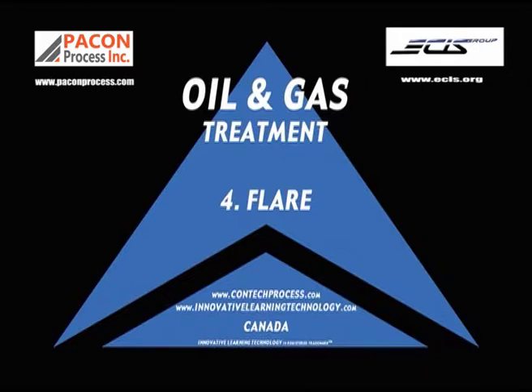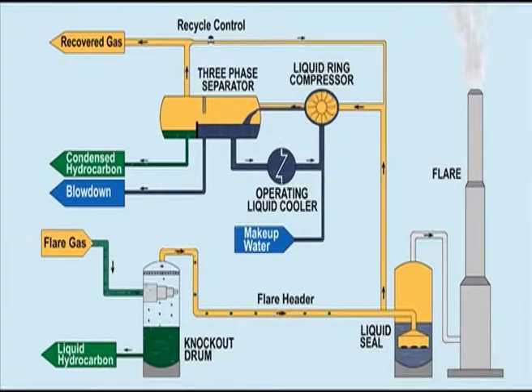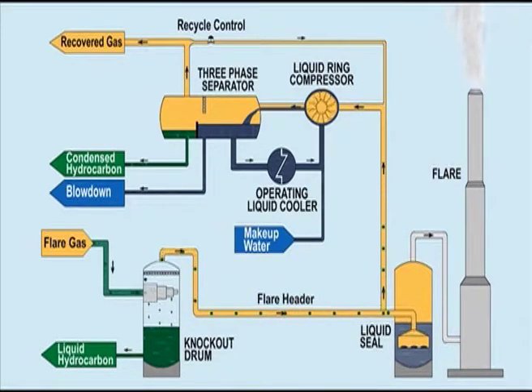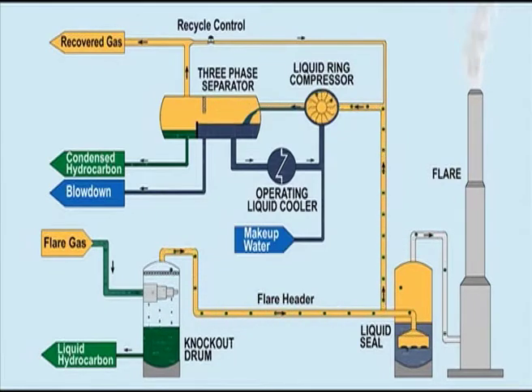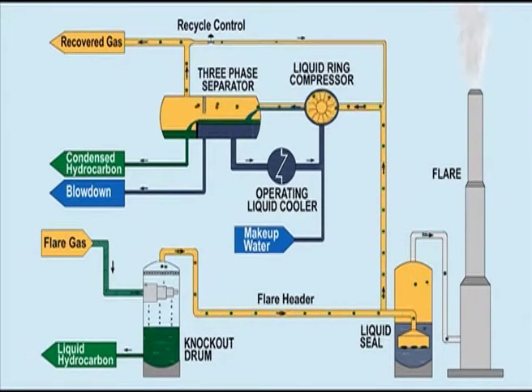Flaring is the disposal of waste gases by burning. Historically, gases are discharged to atmosphere and pollute drastically. Dry gas normally burns through a vertical stack while wet gas is streamed horizontally into a water tank or to an in-ground pit prepared for this purpose. The flare should be installed downwind of the process facility, away from people, to prevent damage caused by open flame.